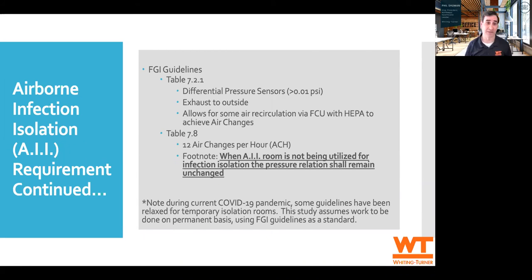Nationally, there have been some guidelines that allowed for some of this during this pandemic. However, if you look specifically at the FGI guidelines, it states that the pressure relationship of all AII rooms shall not be changed when not in use. Like many other things within the guidelines, this is to reduce the opportunity for mistakes. It's the same reason why we put hand wash sinks on the same wall, so that when nurses come in, it becomes an automatic routine.